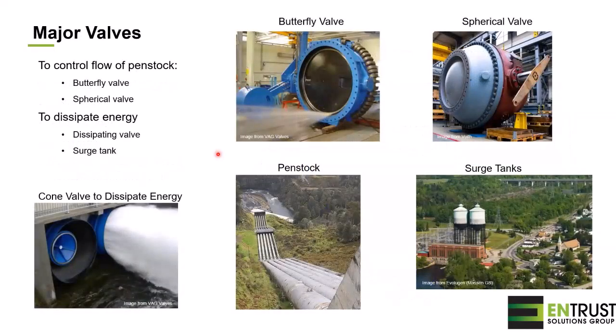We can also find major valves in power plants. These are mainly required for the penstock. At the entrance, we will find either a butterfly valve or a spherical valve. And we will also need an energy dissipating device because the pressure will build along this penstock, and if we have a shutdown of the turbine, we need to be able to dissipate this energy. So from time to time, we will find at the exit of a plant a cone valve to dissipate the energy. And sometimes we will also find a surge tank.